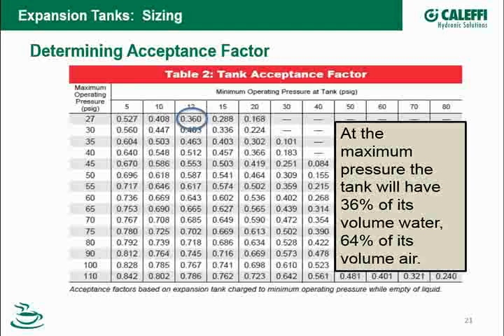Now, an important point to remember is the pressure in your system will change with temperature. Everybody's like, I've heard it before, what's the expansion tank doing? I've heard people either say or post somewhere that it's holding the pressure on the system constant. Based on the size of the expansion tank, that pressure is going to change as the temperature changes. It may start at 12. It might get up somewhere in the 24, 26 range. It might only top out at 18 or 19. But as that water expands, you will find the pressure in the system changing. Questions about that?